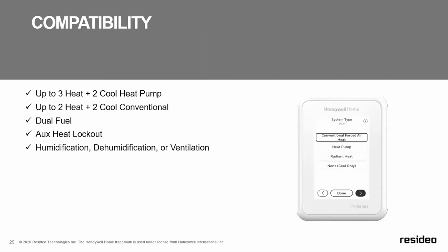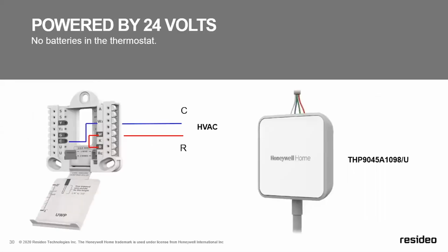The T10 has the capability of operating up to 3 heat, 2 cool for heat pump applications, 2 heat, 2 cool conventional, dual fuel with auxiliary heat lockout, and the ability to control one indoor air quality accessory, hume, dehume, or ventilation. The T10 is powered by 24 volts and requires a common wire. So that would mean 5 wires for heat and cool and 2 more wires for one IEQ option.